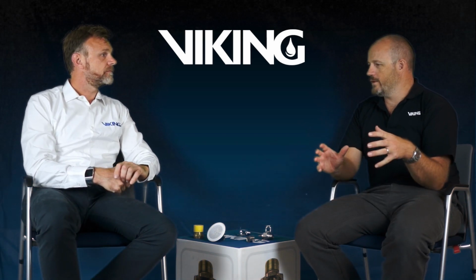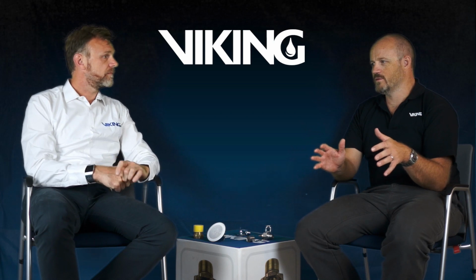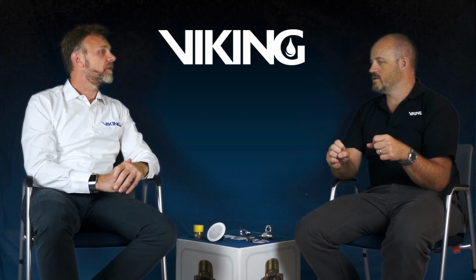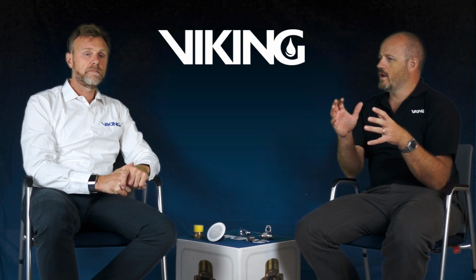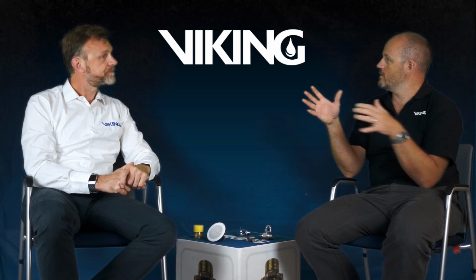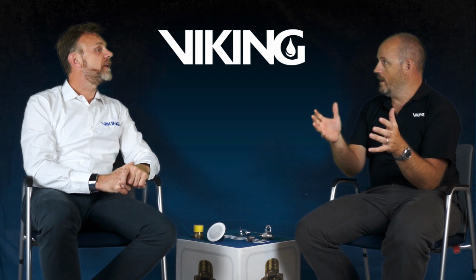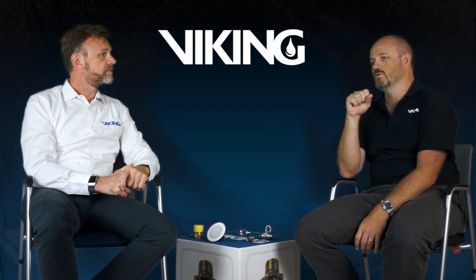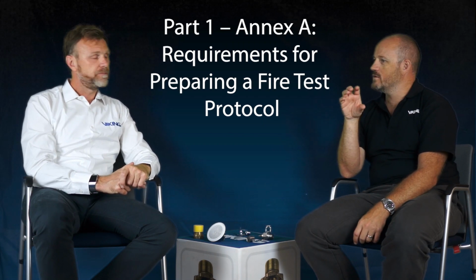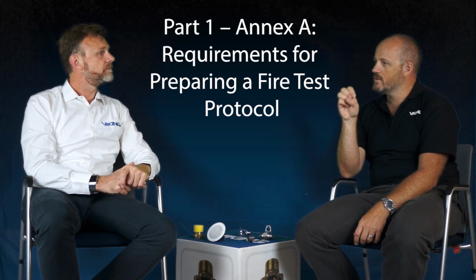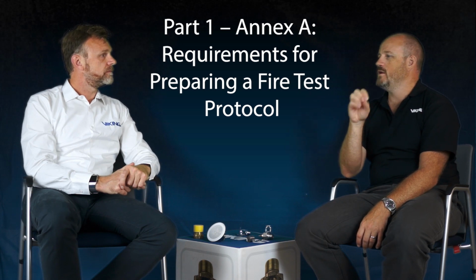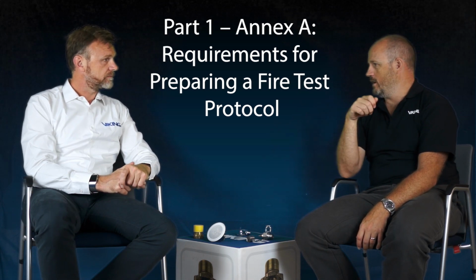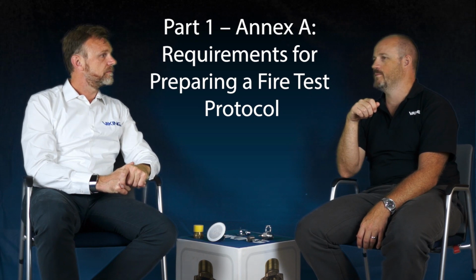Obviously, we've had water mist systems on the market for quite some time now. What I like about the approach of the CEN committee in this case was that they took that into consideration. For those systems that are covering applications that are not in those standards or are not ready yet in those test protocols, we have an Annex A in part one. Annex A includes a set of requirements that an approval body needs to meet when they're writing and defining a test protocol for a system.